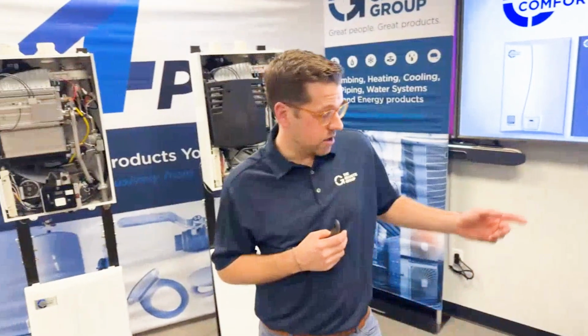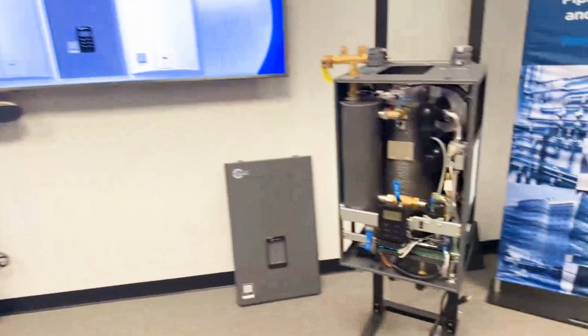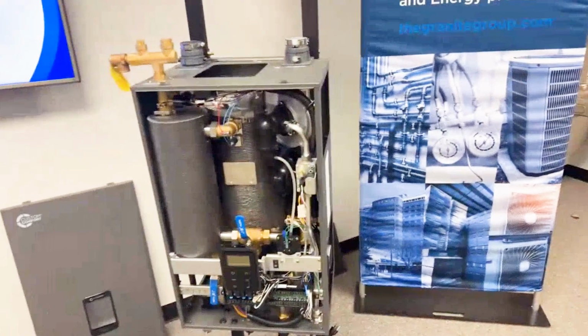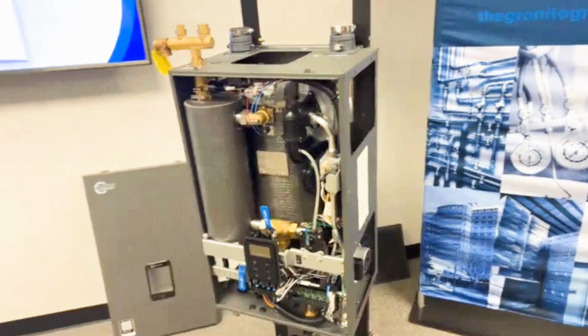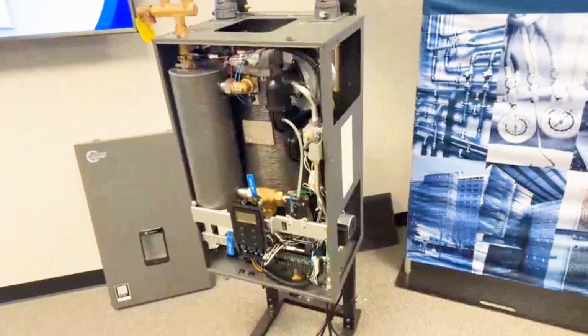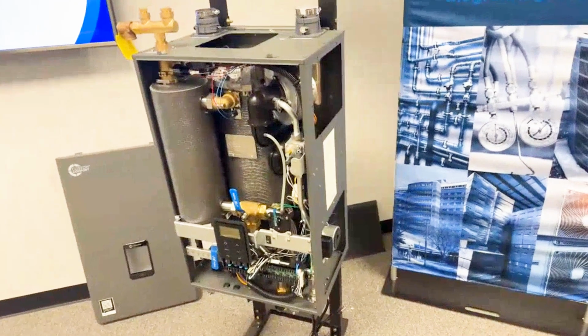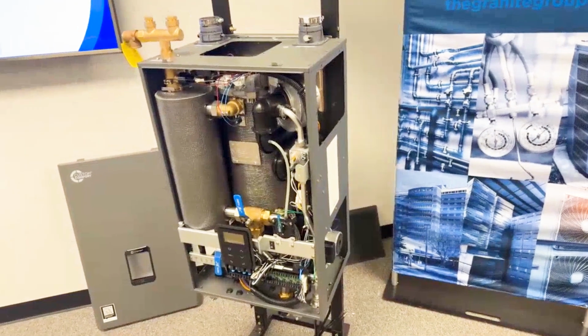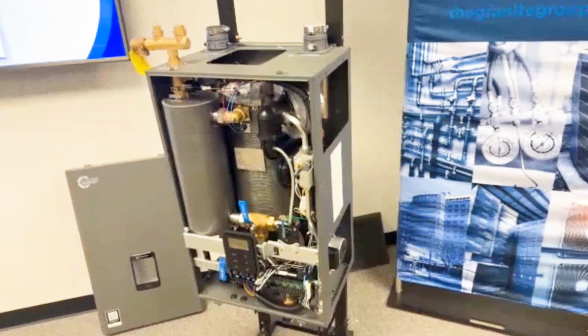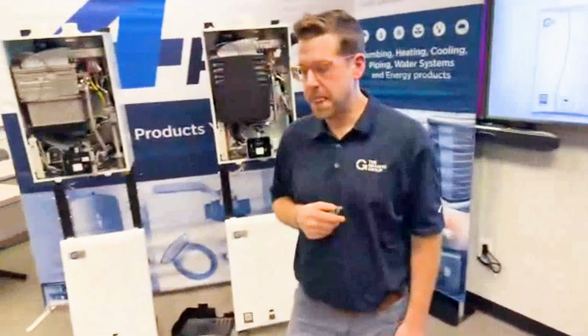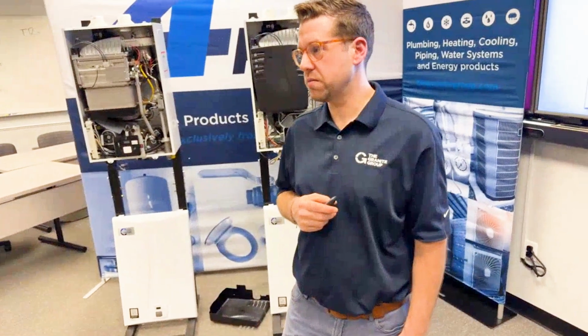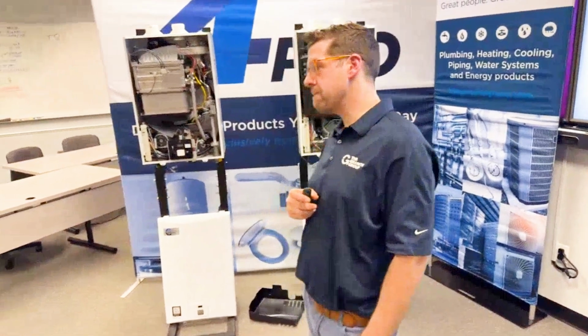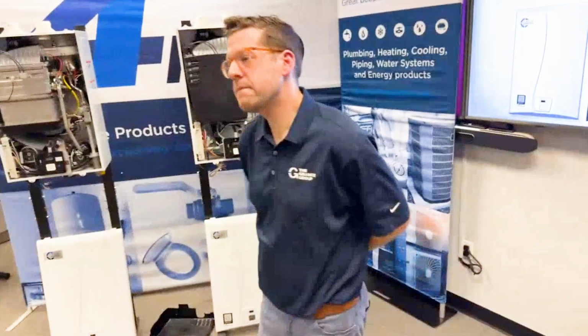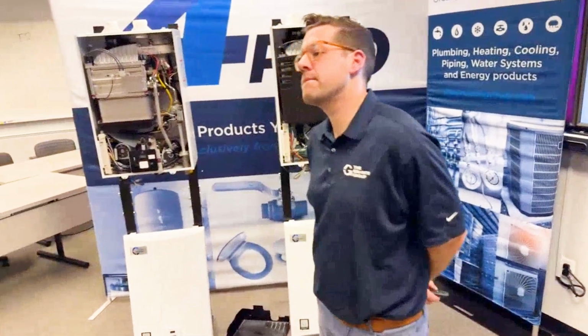On the fire tube combi, the primary pump of that boiler is just flowing through the buffer tank and the fire tube heat exchanger. Domestic recirc will be done via an external pump, but we've got a dedicated tapping for it there. But you are going to need that external domestic recirc pump. Yes. And Rob wants to know, are all models mass approved?